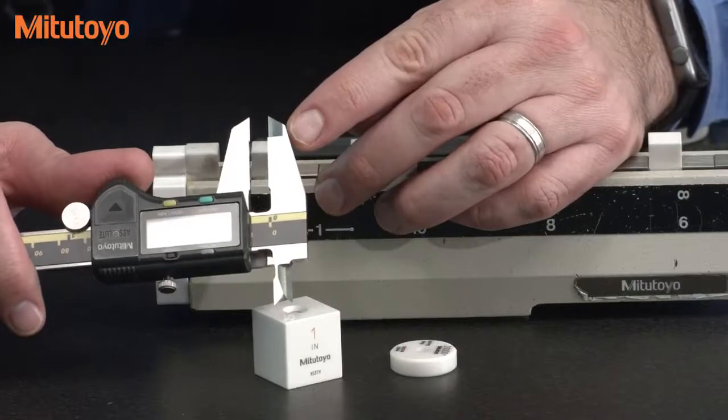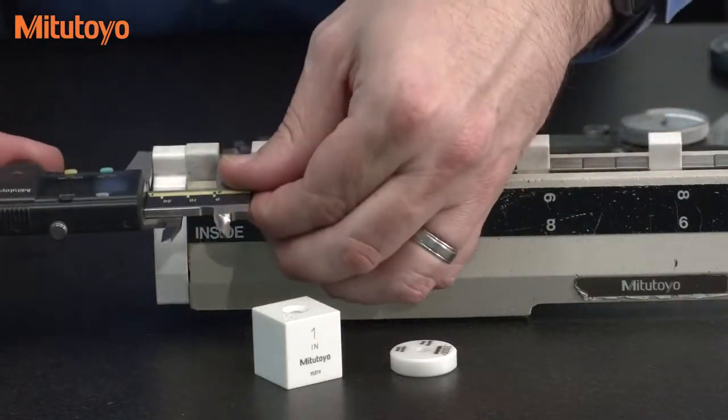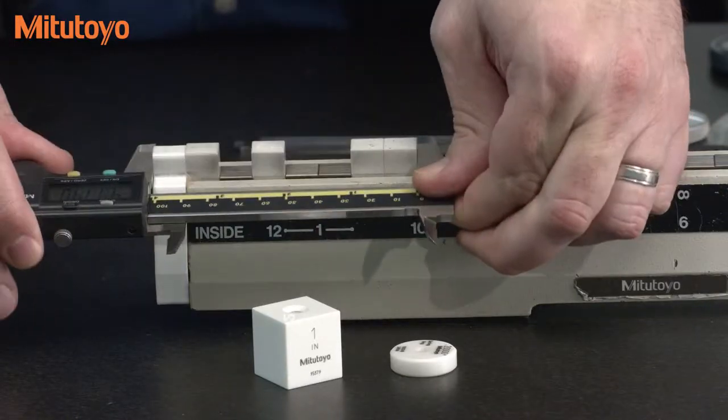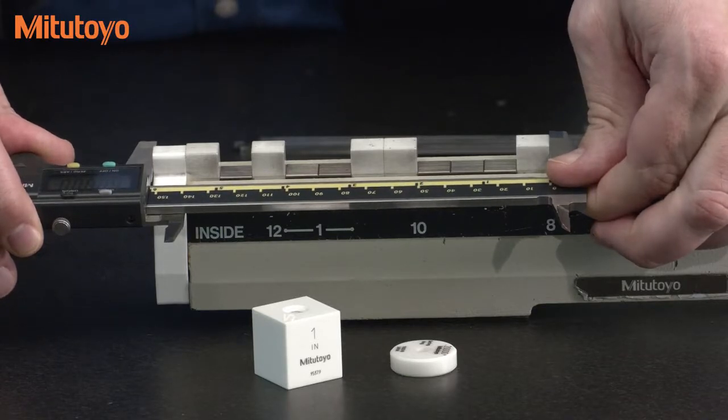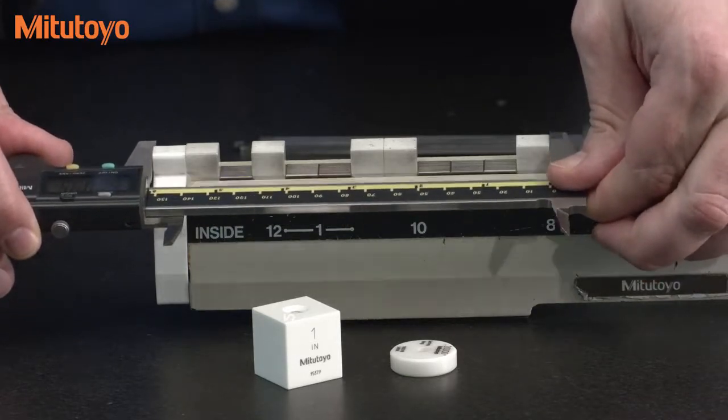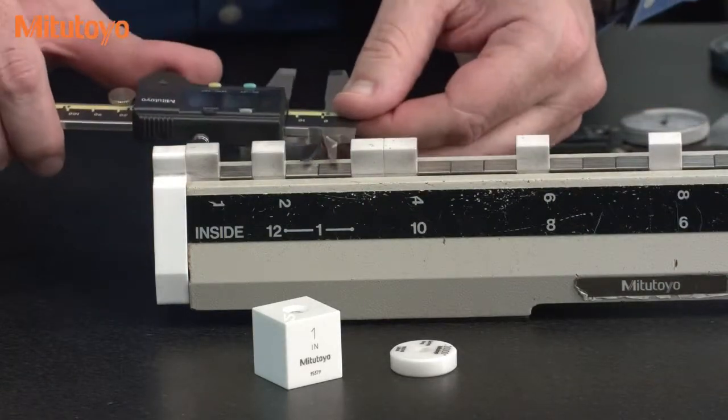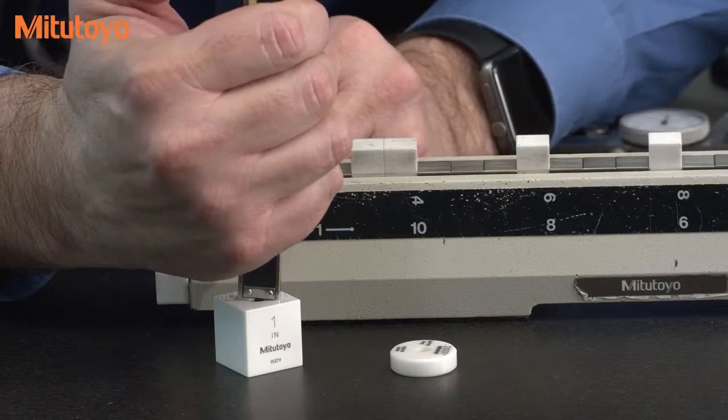For the outside jaws we take a series of measurements over the measuring range: one inch, two inch, four inch, six inches, and we also vary where we are across the jaws. Then we do an inside measurement, one inch like this, then for the depth bar we do a measurement like that.